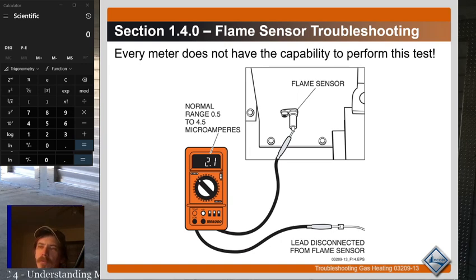But if that doesn't do it, if cleaning the flame sensor doesn't fix it, then you really want to check the signal from the flame sensor to the system, because it could be that something's wrong with the board, or it could be that you just don't have a good ground with the flame sensor. It could be any number of things. But if you're getting proper microamps from a flame sensor, then you need to look elsewhere than the flame sensor. And it's very important to do that, because you will run into weird situations with bad circuit boards and stuff where this doesn't work, because a flame sensor puts out a very small amperage. You measure the signal in microamps, okay?